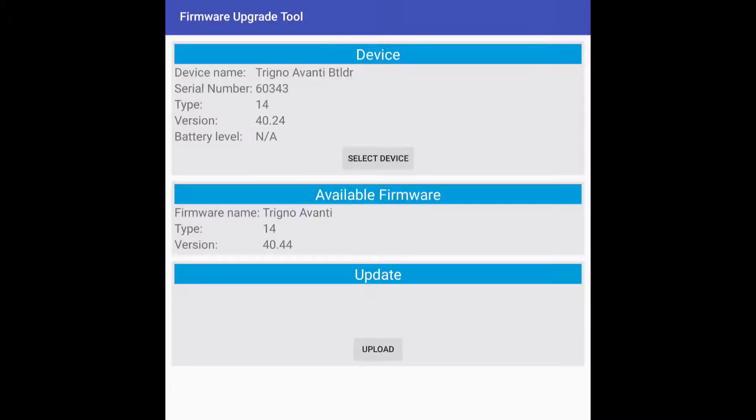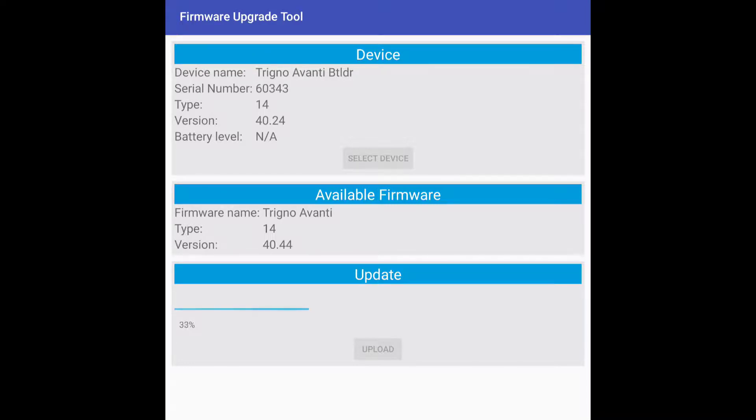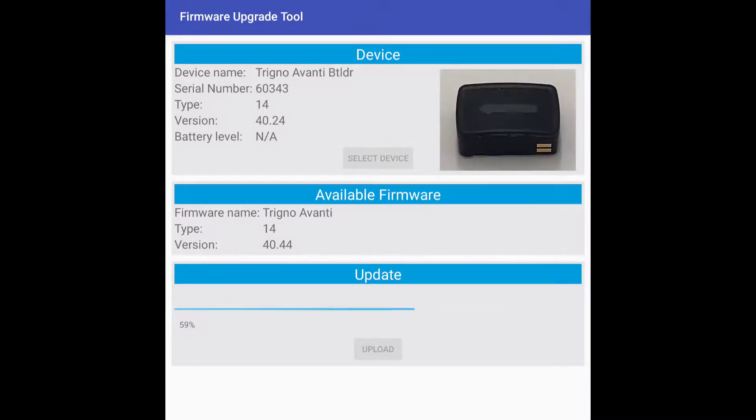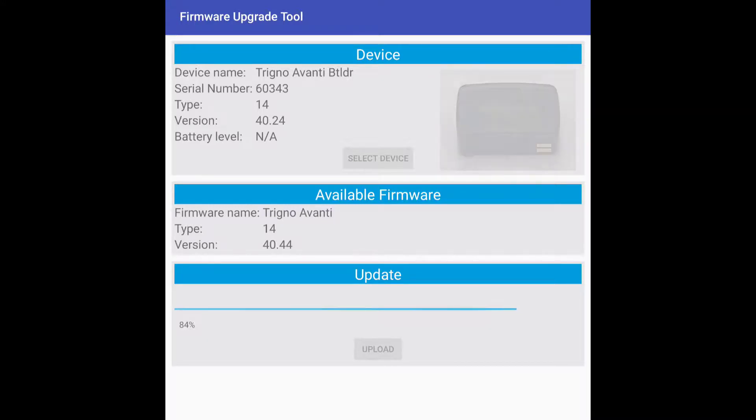While updating, do not return the sensors to the dock and do not close out of the firmware update application. This process may take several minutes to complete. Note that the sensor will flash green when the update starts, magenta and blue during the update, and green when finished.